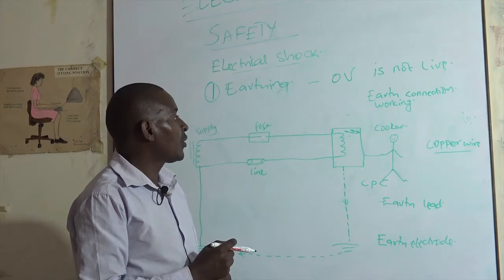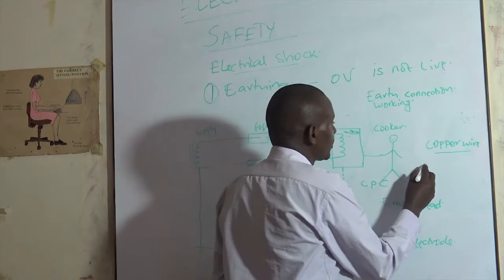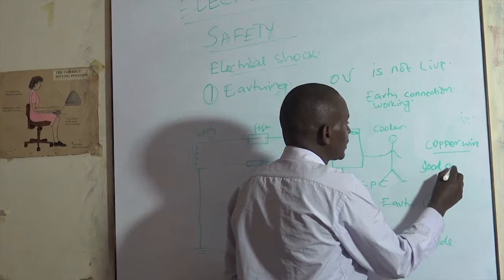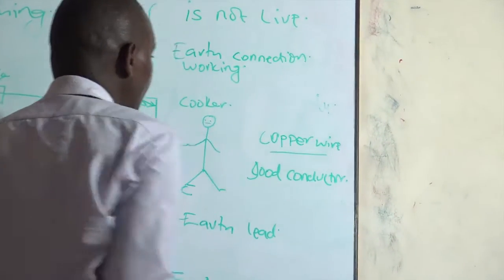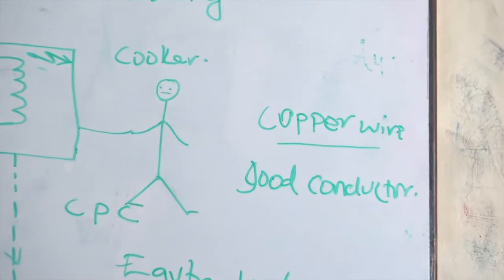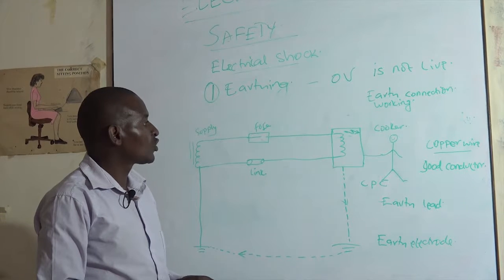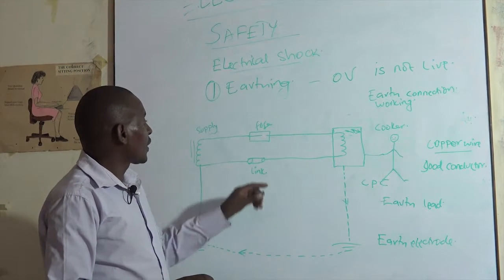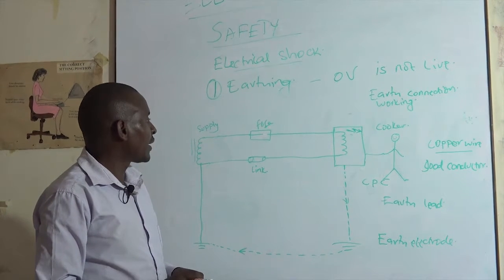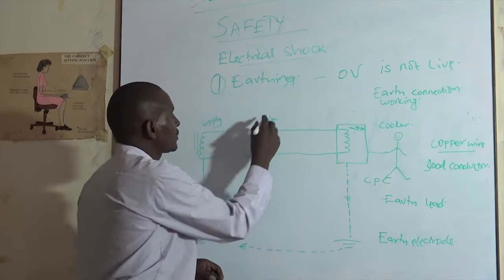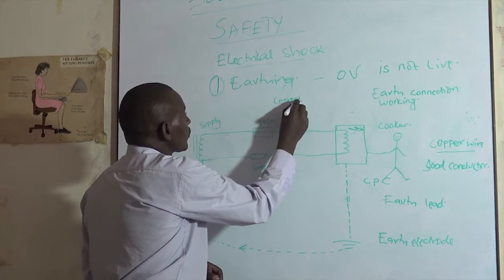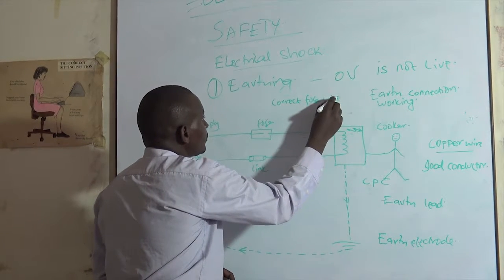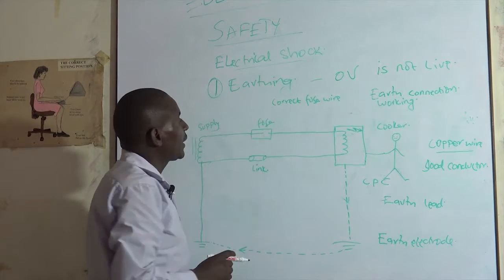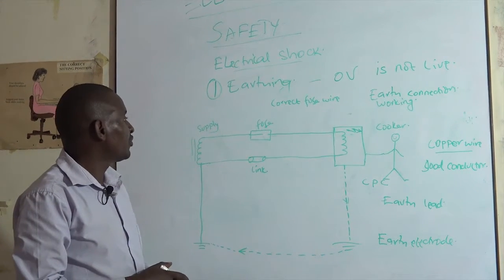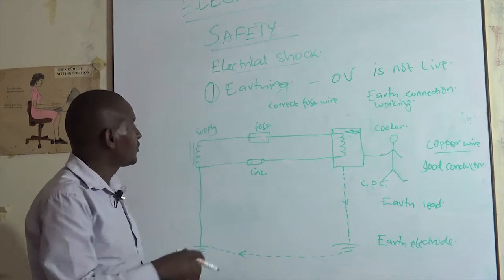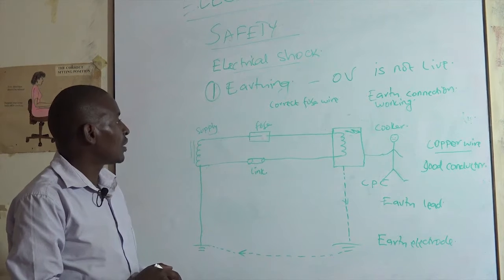What the copper wire does is, copper is a good conductor, and as such, even if it is carrying a high current, it might not be able to disconnect the circuit. So what should happen is, if the fuse is blown for one reason or another, make sure that you either get the correct fuse wire or replace it with an equivalent cartridge type fuse. This will ensure that the safety of the installation is still good.